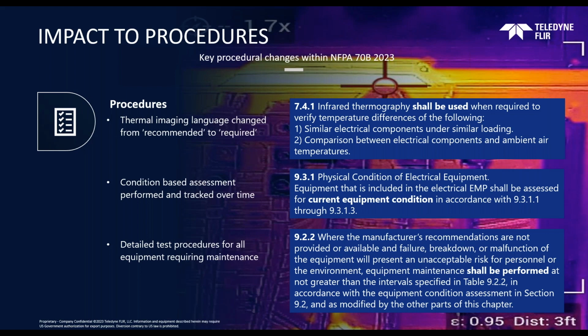So basically it's going to provide you the tasks that need to be done from an electrical maintenance perspective, and how often they need to be done based on category 1, category 2, and category 3. It's very explicit and provides really good guidance for organizations looking to engage or get started on this effort. Really important to note here, at a minimum, regardless of condition, every 12 months will be required for these inspections.